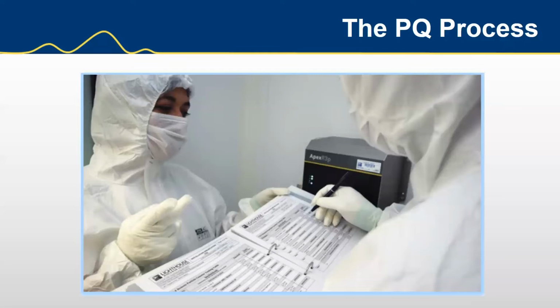You know, customer end user participation in the IQ is an absolute must. Valuable knowledge is picked up during the IQ and OQ and will help the customer develop a robust PQ. The PQ is driving the car and making sure you can drive without crashing and testing every function of the car.